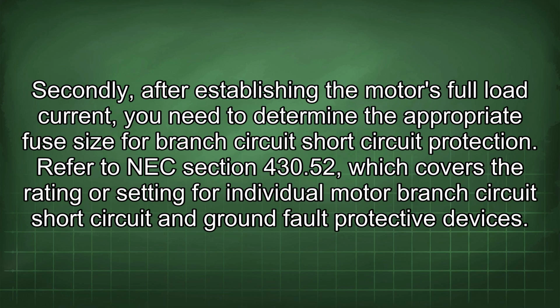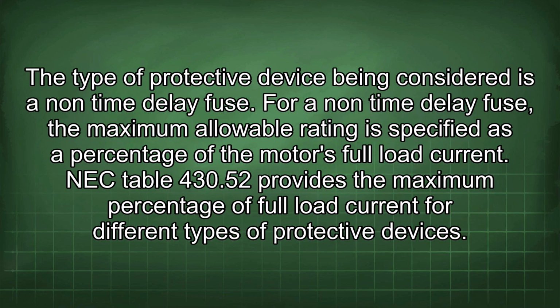Secondly, after establishing the motor's full load current, you need to determine the appropriate fuse size for branch circuit short circuit protection. Refer to NEC section 430.52, which covers the rating or setting for individual motor branch circuit short circuit and ground fault protective devices. The type of protective device being considered is a non-time delay fuse.